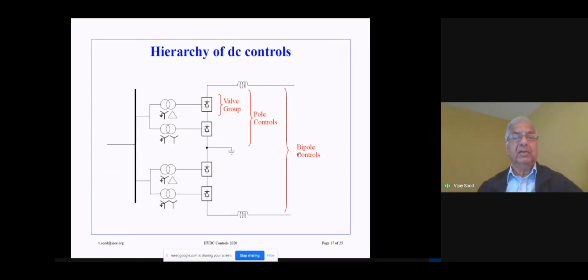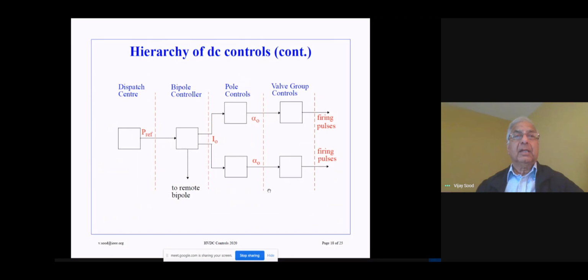So we have three levels of controls. So here are the 3 levels of controls. We have a dispatch center which will give us a power reference order. This will be sent over to the bipole controller, which will communicate that information to the remote bipole. From here, we will generate the current order. So we need to have a voltage measurement to divide the power by the voltage to generate a current order. This will be sent to the 2 pole controllers, and then this will be split into 2 for the valve group controllers. So this gives you the hierarchy of the controls. So these terms, the bipole controller, the pole controller, and the valve group controllers are shown in this graphic.